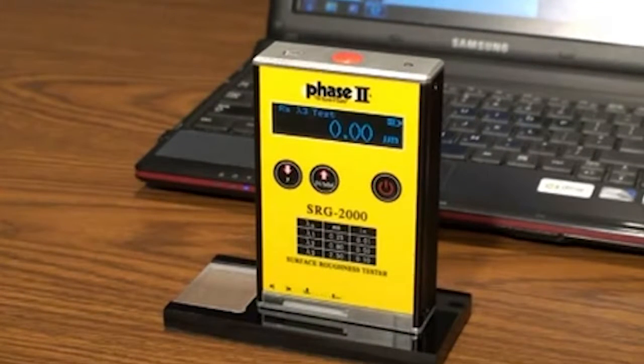There are certain criteria that need to be met in order to operate the SRG2000. You may look into the detailed specifications that are published either in our catalog, website, or operational manual for more specific information. These include maximum surface roughness of 10 micron or 400 micro-inch.